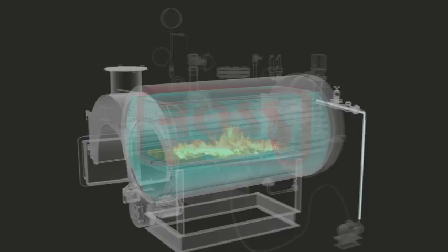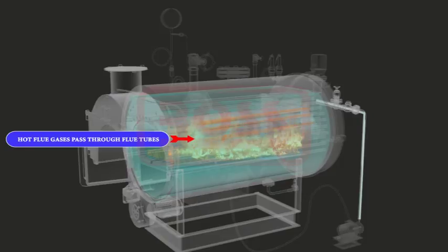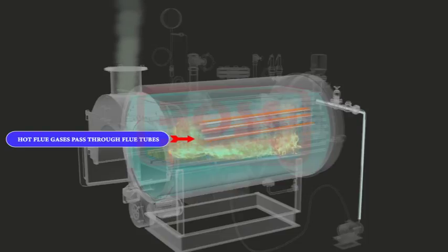The fuel bed is then ignited manually and the ID fan is started to provide necessary air draft for combustion. The furnace is heated up and hot flue gases pass through flue tubes for further heat transfer to water stored in the boiler.